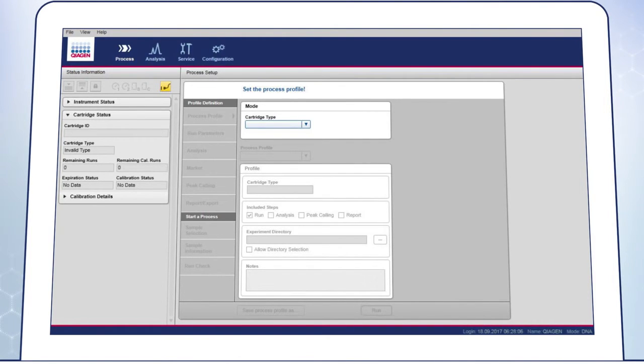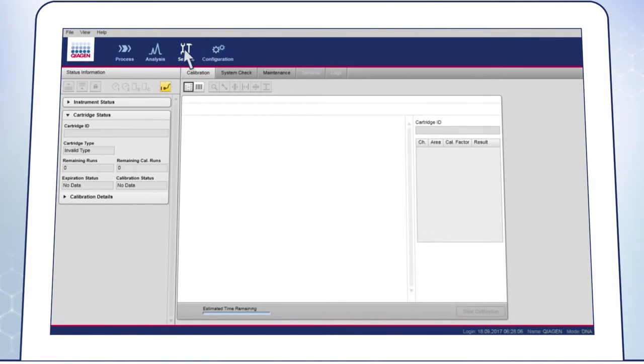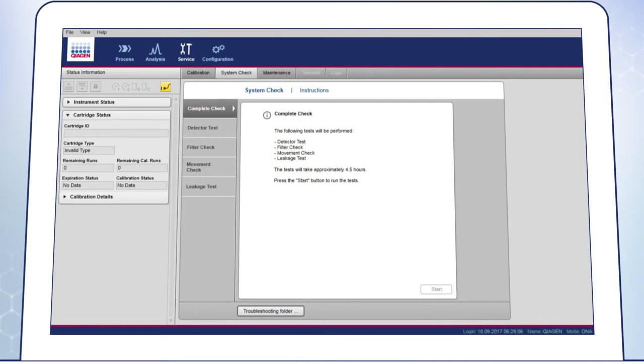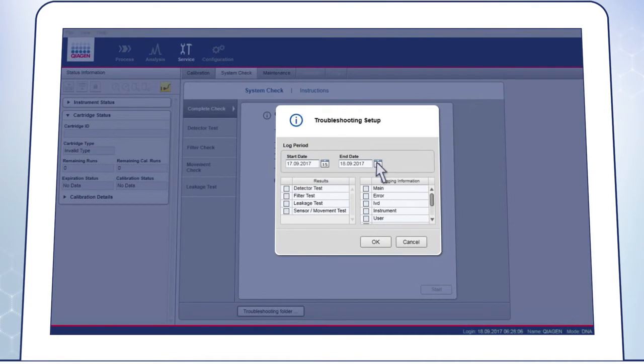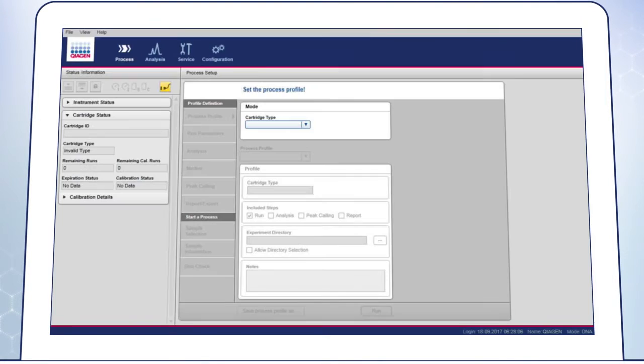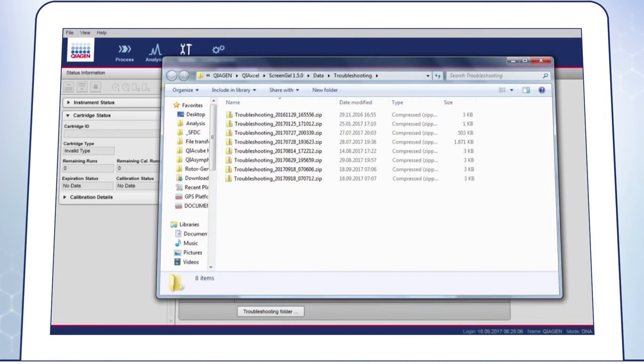1. Troubleshooting folder. In case of communication issues or if a system check was performed, please create a troubleshooting folder by going to the service environment and go to the System Check screen and click on the Troubleshooting Folder button below. Select the start and end date. Select the test on the left side if one was performed. On the right side, always select Main Error IVD and Instrument. Click OK. Then go to File. Open the data directory and troubleshooting and then add the appropriate troubleshooting zip folder to your email.